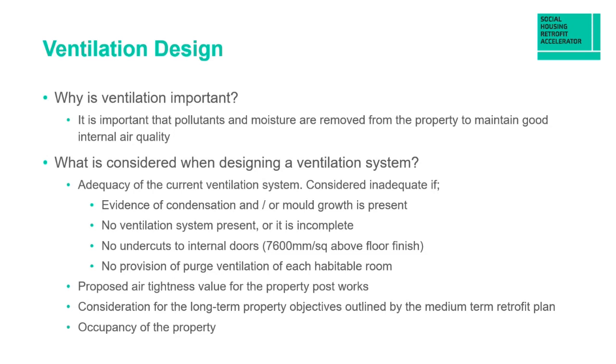And when designing a ventilation system under retrofit, then the adequacy of the current ventilation system is taken into account. And it's considered inadequate if there's any evidence of condensation and or mold growth in the property, and that would be identified through the risk assessment. If there's no ventilation system present at all, or it's incomplete, there are no undercuts to internal doors, or if there's no provision of purge ventilation for each of the habitable rooms.